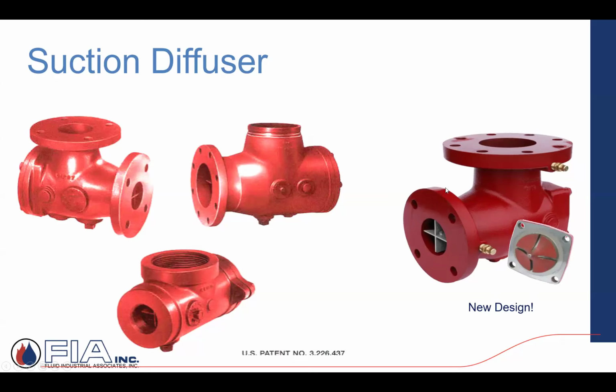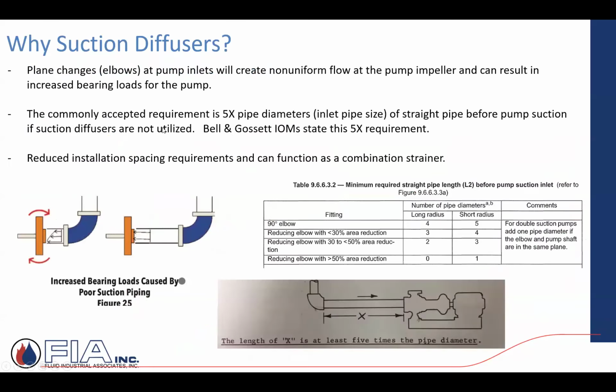They're just showing off to the right here a newer design. But I just want you to pay attention to these little, they call them vanes, that are sitting inside that volute. That's very important. That's the whole kind of secret, if you will, of the magic behind what we refer to as a suction diffuser. And so real quickly, why suction diffuser? Well, when you're changing, in this case here, they're saying a plane change. So maybe I'm coming down vertically, and now I'm going to enter into that end suction. I'm going to change my direction.